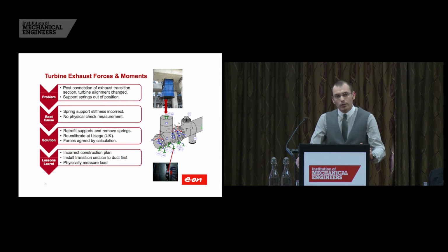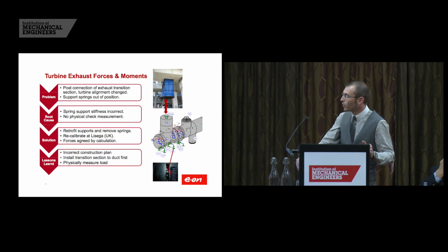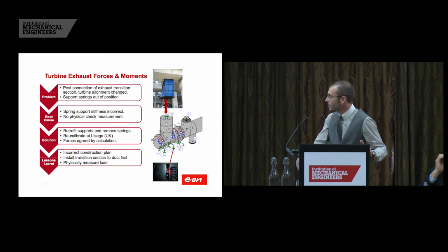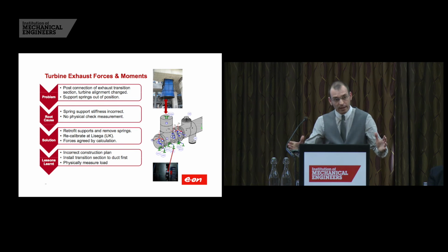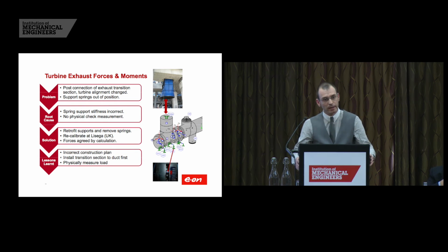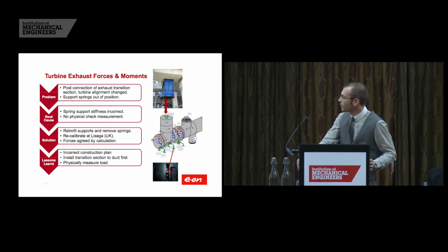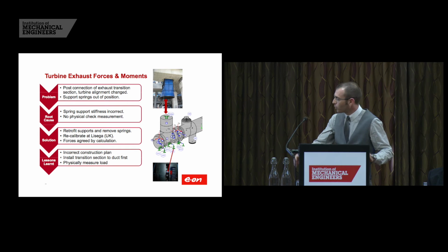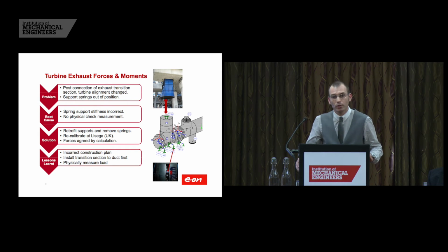The second main challenge of the contract was one of the first erection activities. Once the steam turbine was erected on the turbine table, the first section to be installed was the turbine exhaust transition section. This converts the rectangular duct to a circular duct to allow connection to the ACC duct. On installation of the ACC duct provided by GEA, the spring supports below the duct were released, and there was a noticeable change in the alignment of the steam turbine.